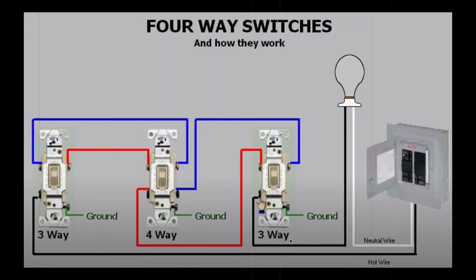Here is a picture of how normal electrical wiring looks for a four-way switch. You have the power outlet box, and from there the hot wire comes out and goes all the way to your third switch, which powers your four-way connection. When you flip the switch up and down, the electric current goes through either the blue line or the red line—these are called the travelers—and they go into the middle switch, which has four terminals.